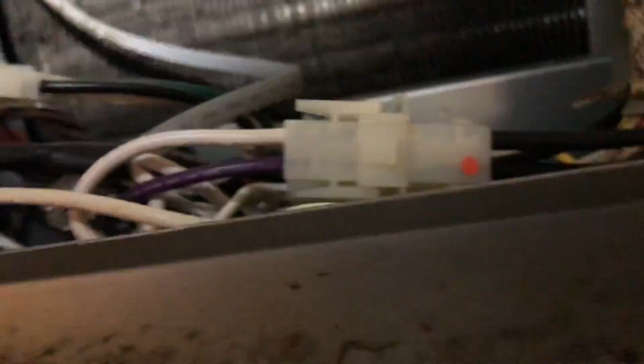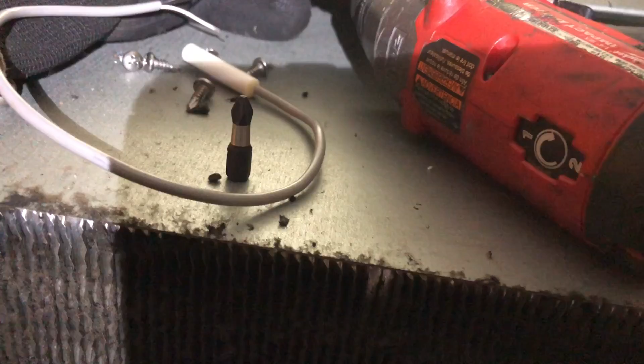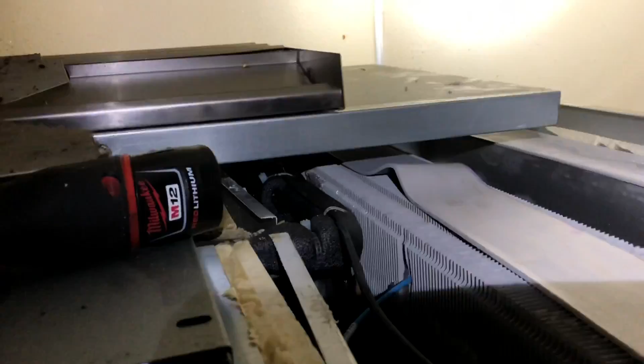You guys know I always harvest parts. I got a sensor that's really close to the ohms values of the Traulsen. Shame on me, I don't have a Traulsen cabinet sensor on my truck. To get that sensor out - see how tight it is down there? Get a little ratchet, the 1/4 inch, and I got those little bits, the Phillips, we'll see if that fits in there to get that out, so you don't have to take the whole evaporator out. We're in tight quarters today.